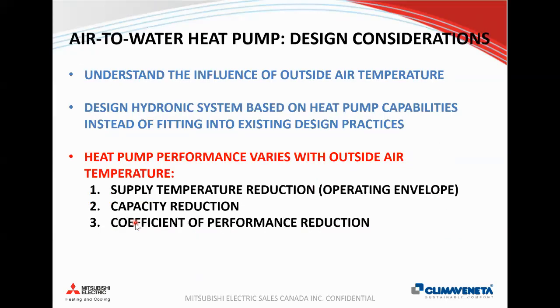So basic design considerations, it's really a heat pump is influenced by the outside air temperature. So it's a little bit different than designing with typical boiler systems. So for any designers or contractors that are on the call today, if you are looking at offering this type of system for your clients, it's really important to understand at the start of the design process how that heat pump operates and behaves in the system, and design your system around the capabilities of that heat pump, whether it's retrofit or new construction. And there's kind of three key things that we want to watch out for on the heat pump. So we want to understand how the supply temperature from the machine is going to be affected by the ambient temperature, which is referred to as the operating envelope.